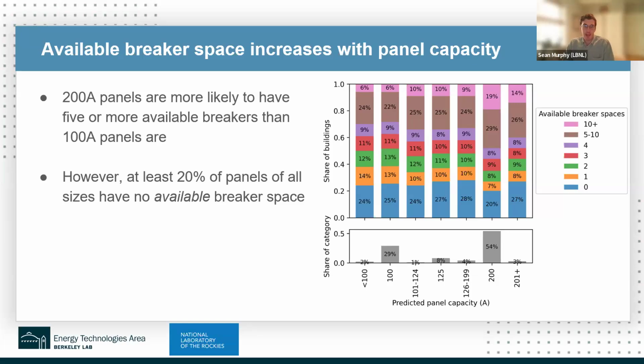However, we do find that at least 20% of all panels of all sizes have no available breaker space. That means there are 200 amp panels that have no breaker space, and there are 100 amp panels that have no breaker space. As I mentioned, that's the blue we see in the figure. So issues with no available breaker space are affecting panels of all sizes.